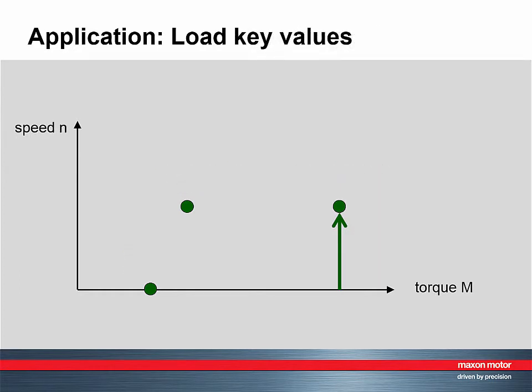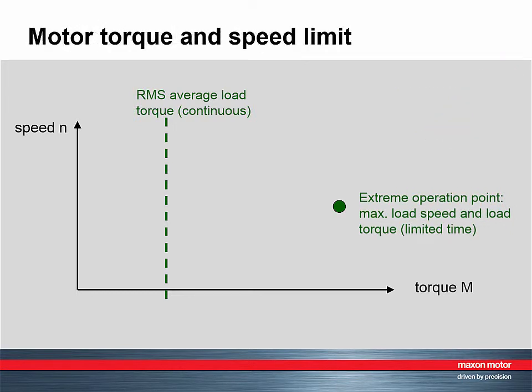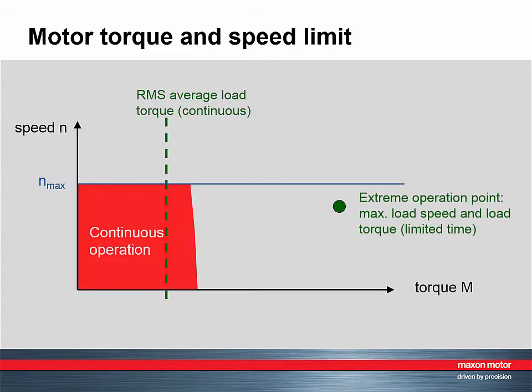Regarding torque, we condense all the operation points into a few key values: the average RMS load torque and the extreme operation point. Let's first look at speed. We need a motor with a speed limit that is high enough to cover all operating points.